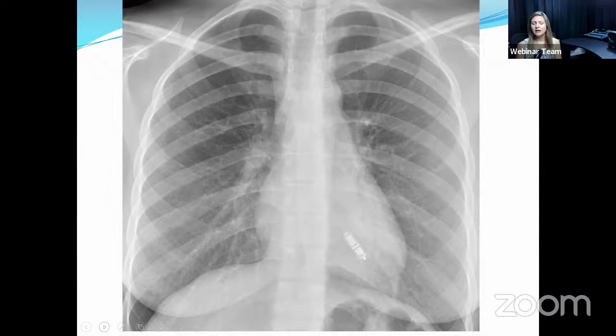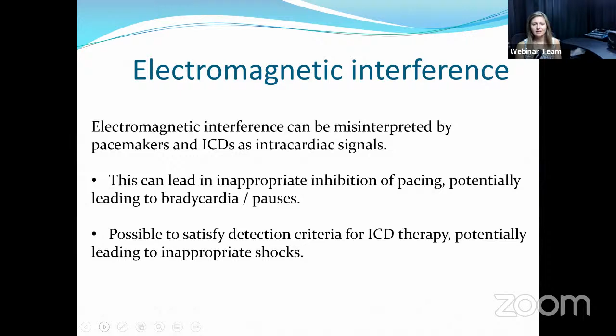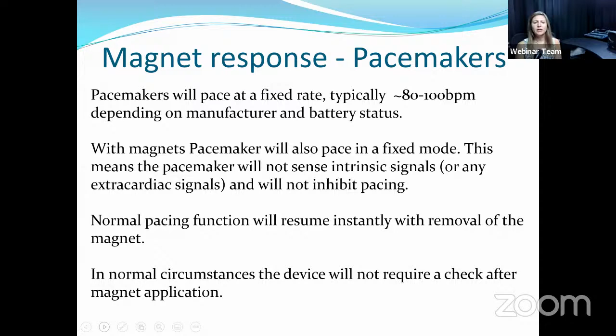defibrillator can misinterpret that. This can lead, in the case of the pacemaker, to inappropriate inhibition of pacing, and therefore the patient can be at risk of bradycardia or pauses. The same can happen with the defibrillator. If they detect a different rhythm, they can suddenly and inappropriately shock the patient. So if you're concerned that this can happen with a pacemaker, we can use a magnet. This will stop the pacemaker from sensing the external signals and it will continue to pace at a fixed rate of 80 or 100 BPM, depending on the manufacturer. The pacemaker will pace in a fixed mode, and in this way will not sense any intrinsic signal and will not inhibit the pacing. Once the treatment is finished, it's important just to remove the magnet, and the pacemaker will immediately resume its rhythm.